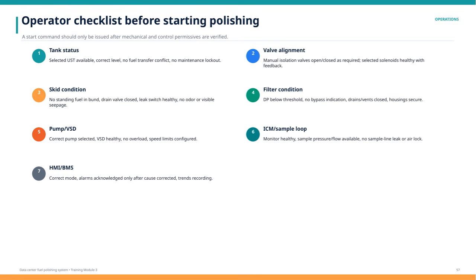Manual isolation valves should be set correctly, and solenoids must be operational with proper feedback confirming their status. Then assess the skid condition. There should be no standing fuel in the bund. The drain valve must be closed. Leak switches need to function properly, and there should be no odor or visible seepage.